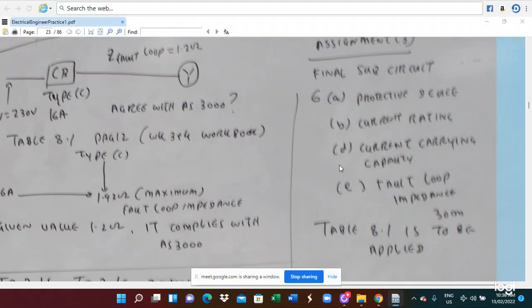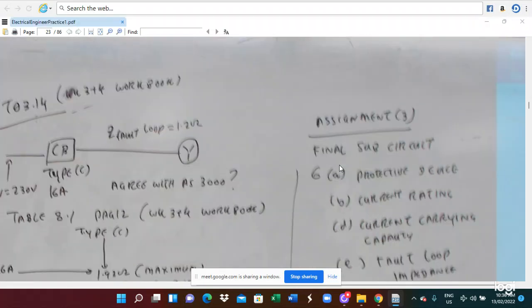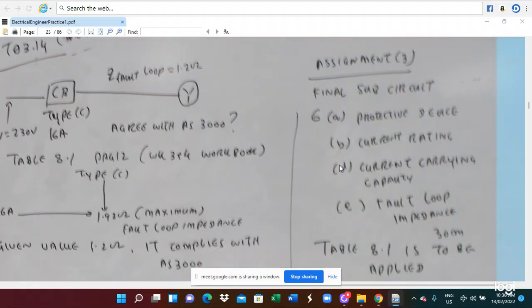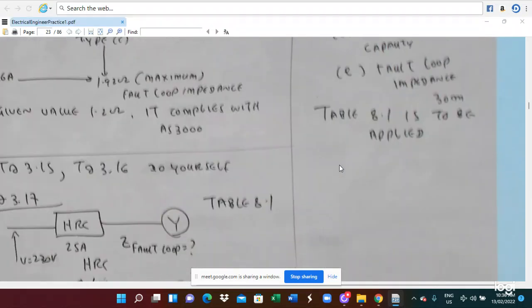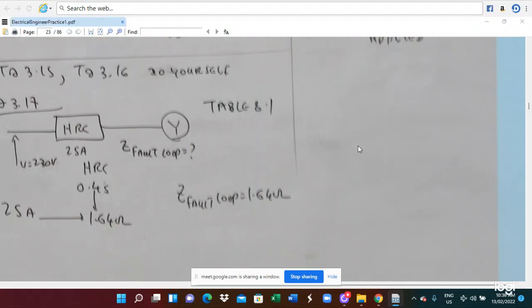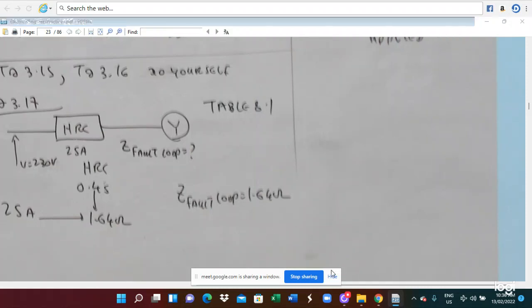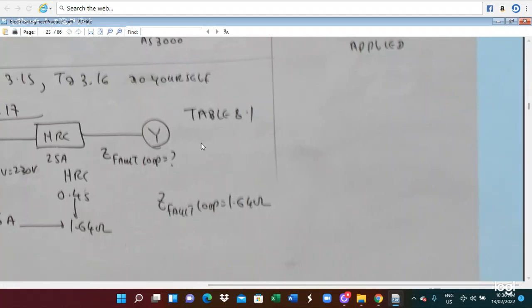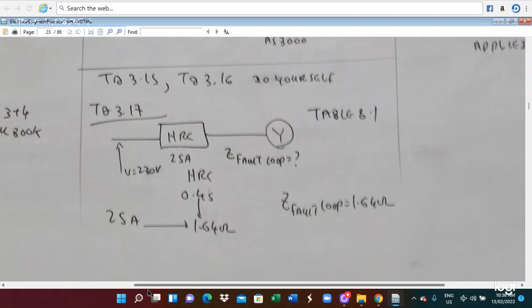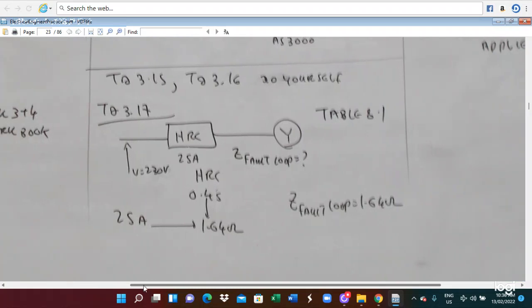So this is the appropriate fault loop impedance calculation. We have to refer to the appropriate fault loop impedance before we start any electrical installation. This is the fault loop impedance, and this is how we do it. You refer to the appropriate AS3000 table.